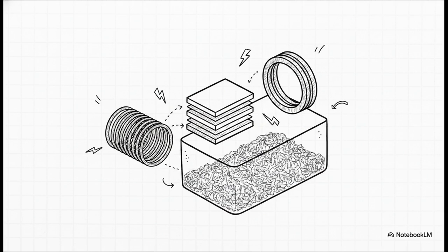Next is the primary winding, which hooks up directly to that terrifying high-voltage line. Then we have the secondary winding, safely connecting to your everyday voltmeters or protective relays. And finally, the unsung hero within the hero, the insulation. Because PTs deal with massive voltages, the windings are completely immersed in oil or fully encapsulated in tough resin to prevent catastrophic sparks and short circuits.